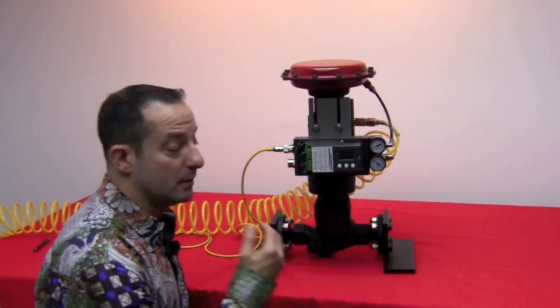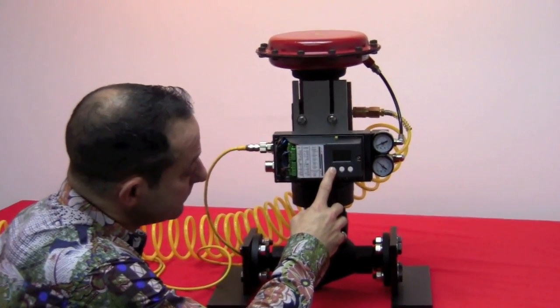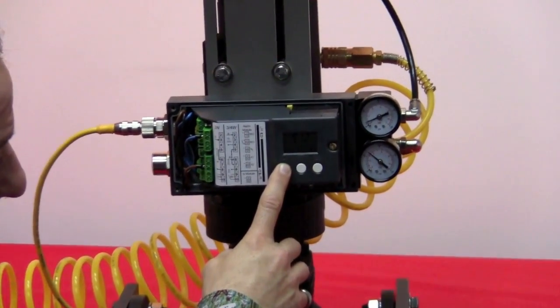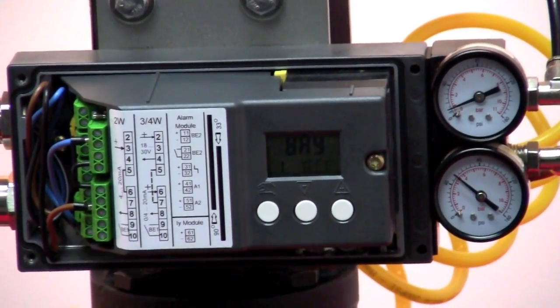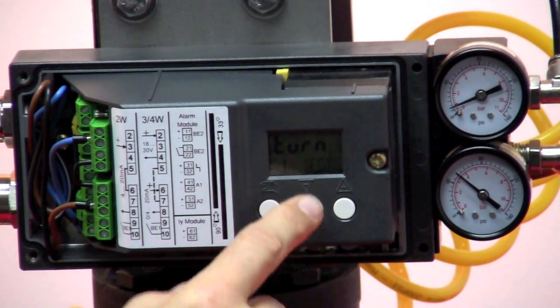Once this is accomplished, you can go into the program menu by holding down the mode key for approximately 4 seconds. And it's very simple. You need to configure two parameters. You need to tell the positioner whether you are operating with a linear or a rotary valve. In this case, I can choose a rotary valve or a linear. I'll choose linear.